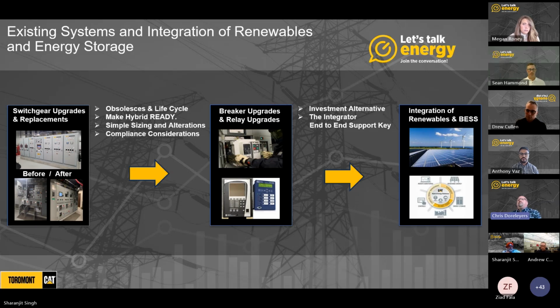So the very first thing you want to do if considering doing something with an existing system is look at the age and potential obsolescence of the components. Going back to the switchgear conversation, let's use switchgear as an example since it's at the core of many of these energy systems. That's a good place to start to see if there's obsolescence. In a switchgear you may have components like a protection relay, a PLC, breakers, and all of these items are subject to being obsolete. So the best thing to do out of the gate is to evaluate all those components to make sure they are not obsolete, and if they are, work up a plan to do a replacement.